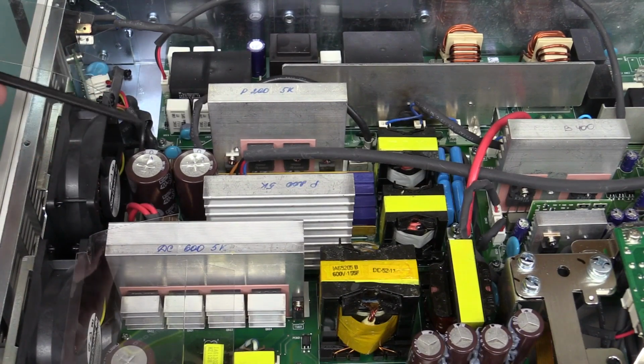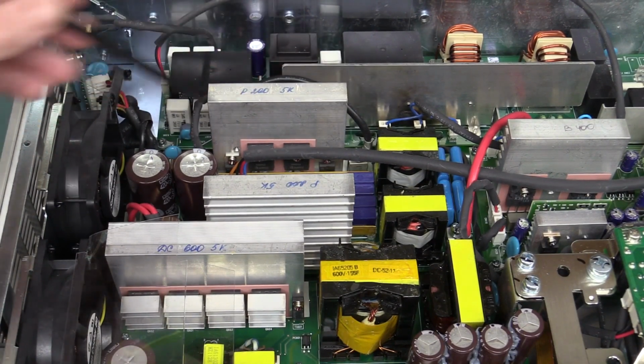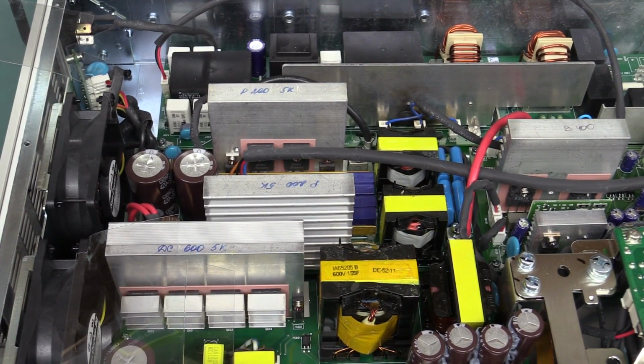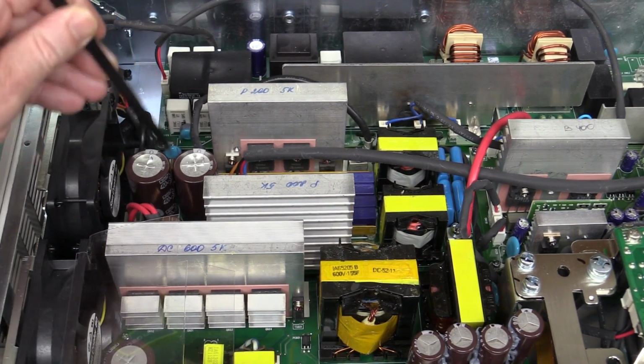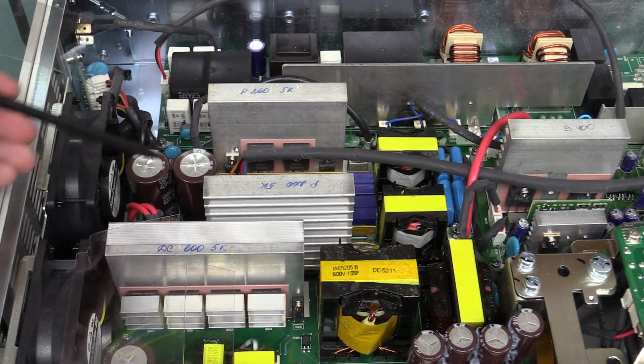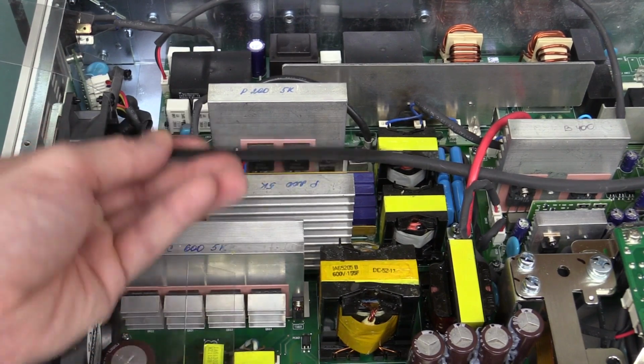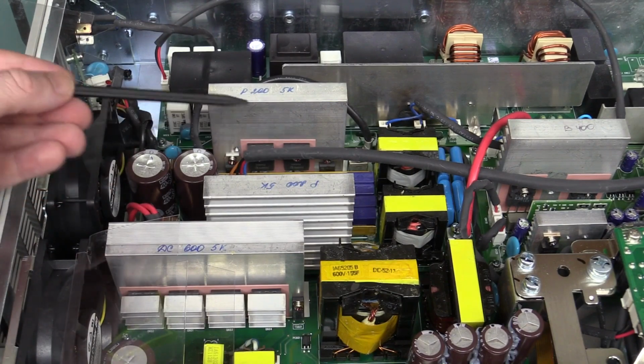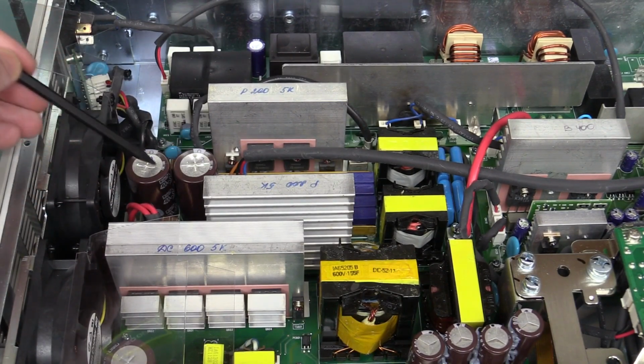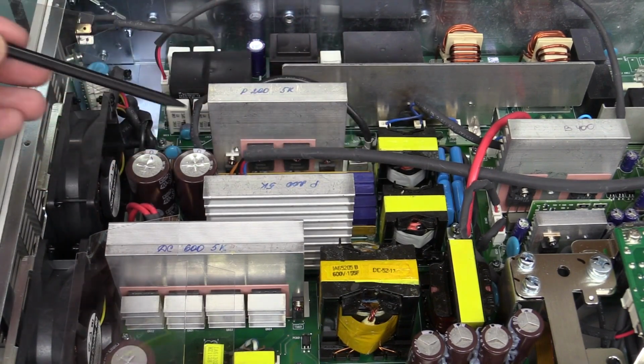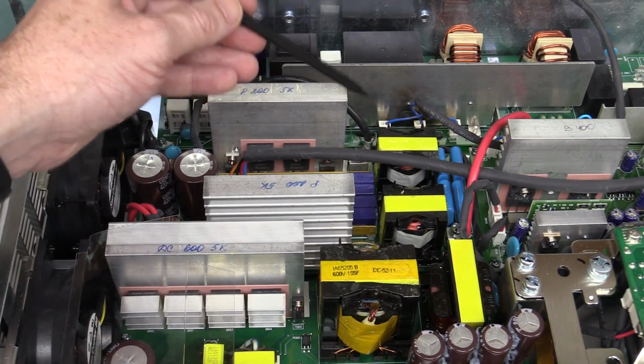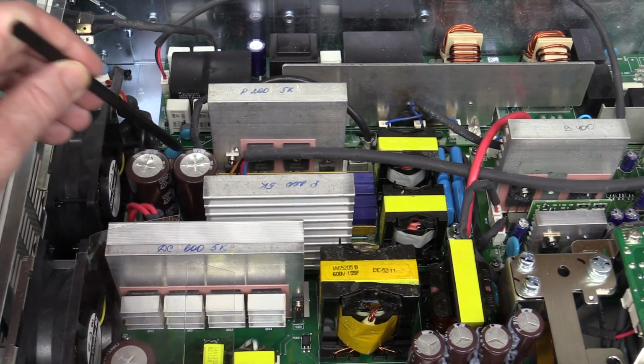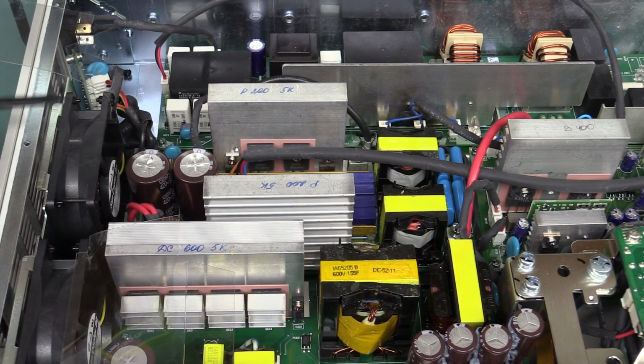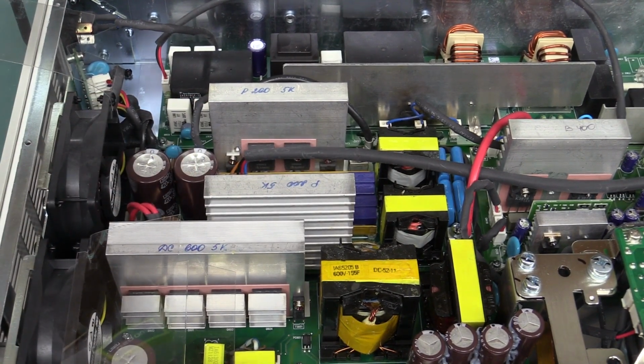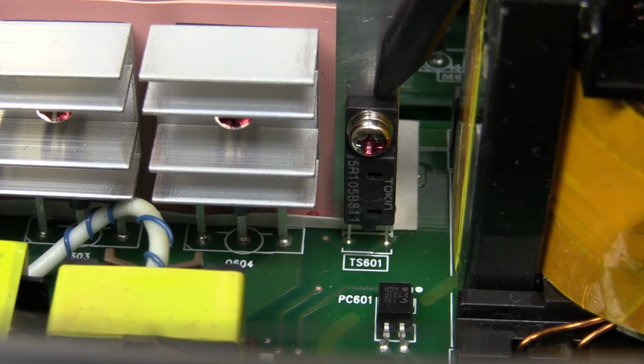And you can see that they've done this absolutely perfectly designed up on the power factor correction board up here. They've got the fan here. It's sucking the air in from the front, blowing straight over the capacitors first. So it's keeping those really cool. And then the 2 heat sinks are aligned in the correct orientation so that the air can flow over the fins and straight out. If you had it the other way, so that these capacitors were over here, like this, then you'd be blowing the hot air onto the capacitors, and that's not good for their life. So you want these caps on the cool side of the heatsink and your airflow like that. Nicely designed. And they've got themselves a little temperature sensor there right on the heatsink.